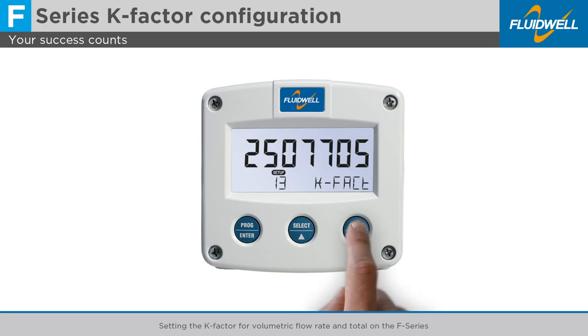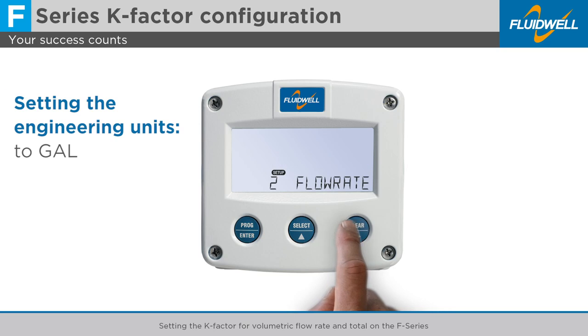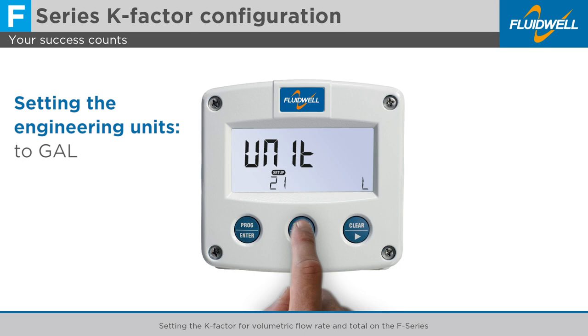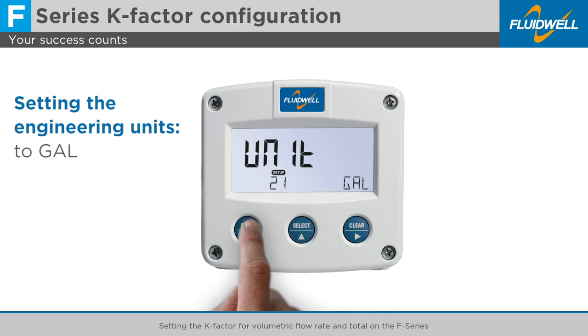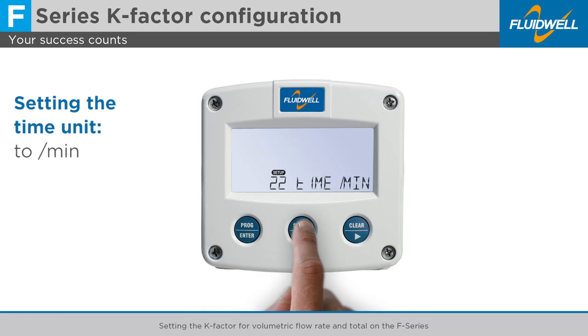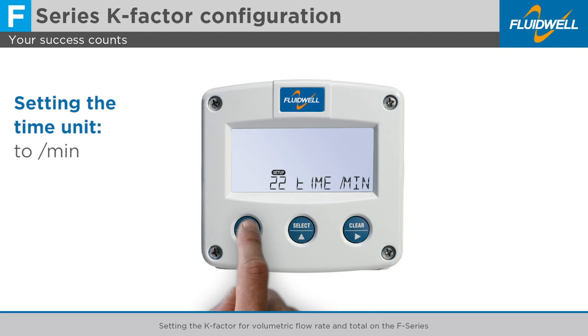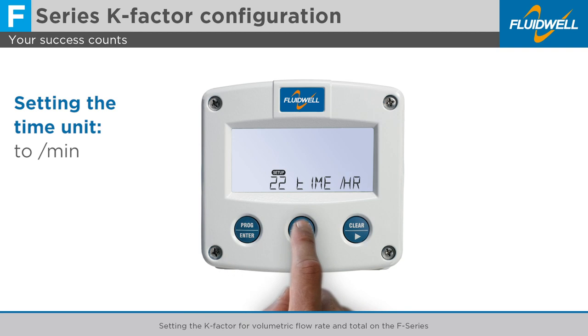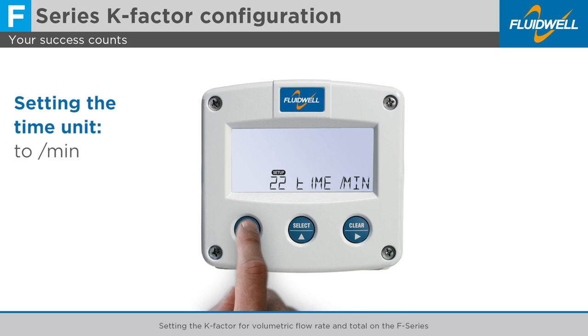Use Clear to navigate to Menu 2, Flow Rate. Press Select to go to Menu 21, Unit. Press Prog to change the engineering units for the flow rate to US Gal. Press Prog to store this setting. Use Select to go to 22 time. Press Prog to change this setting to time per minute. Press Prog to store this setting.